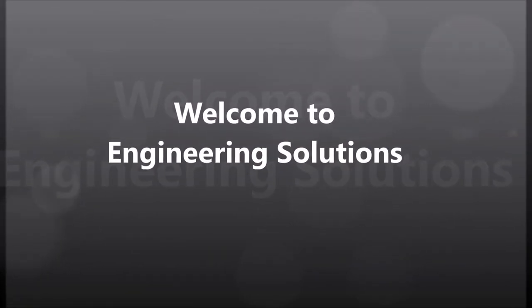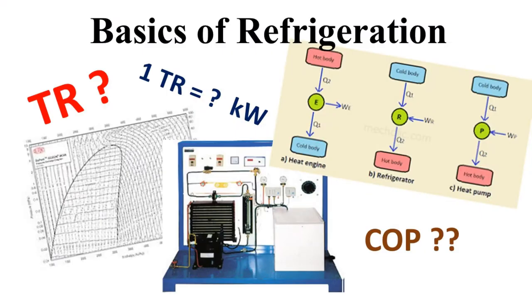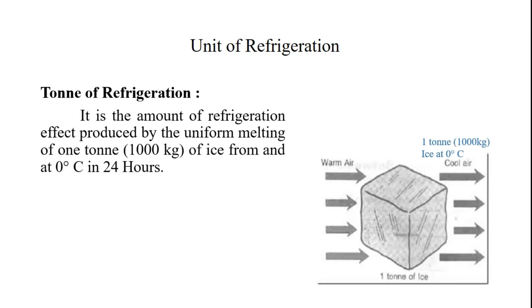Hello friends, welcome to my channel Engineering Solution. In this video we will go through some basic terms related to refrigeration. First of all, we will see the unit of refrigeration. The refrigeration effect, or simply refrigeration, is measured in a unit called ton of refrigeration, also called TR. It is the amount of refrigeration effect produced by the uniform melting of 1 ton of ice from and at 0°C in 24 hours. In simple words, if we keep 1 ton (1000 kg) of ice at 0°C, the cooling effect produced by it in 24 hours is called 1 ton of refrigeration.